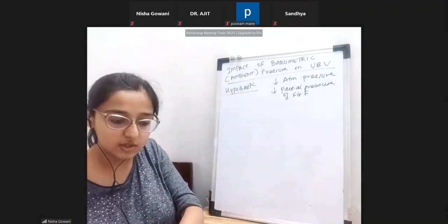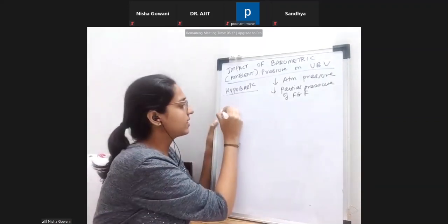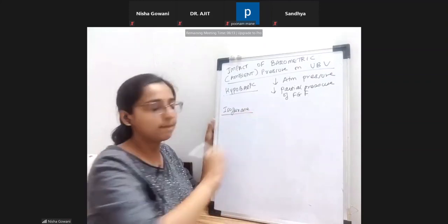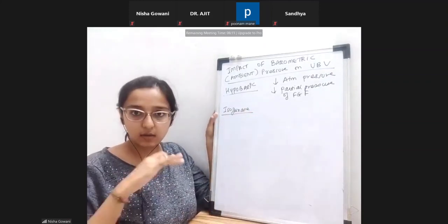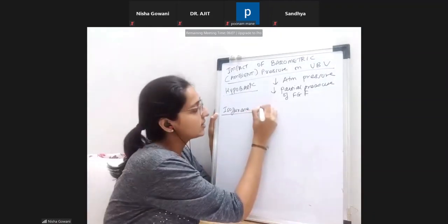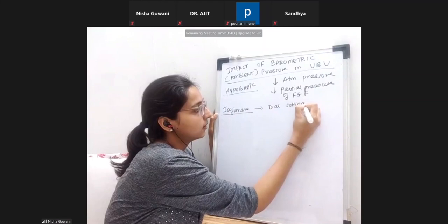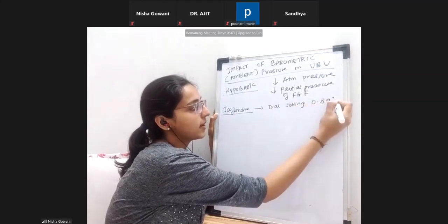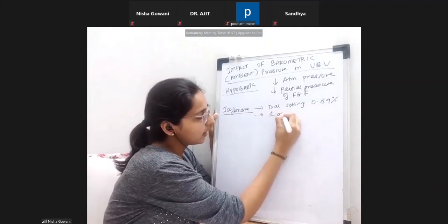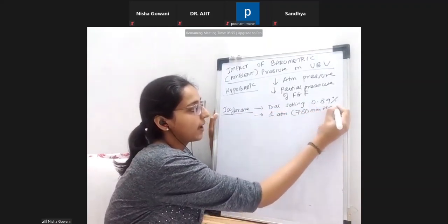Take an example which is from Miller's only. They have taken the example of isoflurane at atmospheric pressure, where we are at 1 atm. The dial setting they have kept is 0.89%. This was an experiment which they had done. And we were at 1 atmosphere, that means 760 mmHg was our ambient pressure.